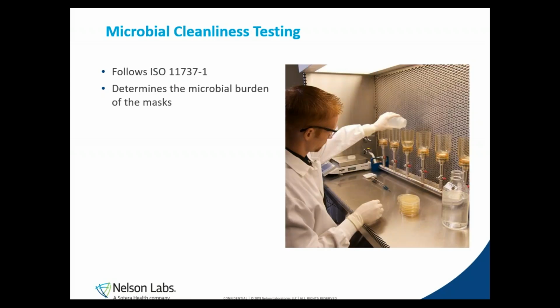Microbial cleanliness testing is required only in Europe, and it determines the microbial burden of the masks, or how many microbes are detected on the masks after they have been manufactured. The masks are submerged in a growth media to extract the organisms, and then the organisms are grown and counted to determine how many microbes were present on the masks.